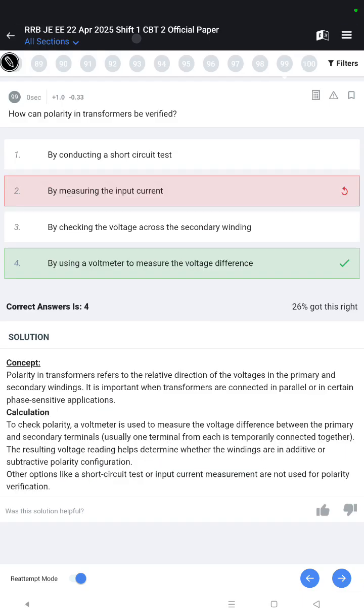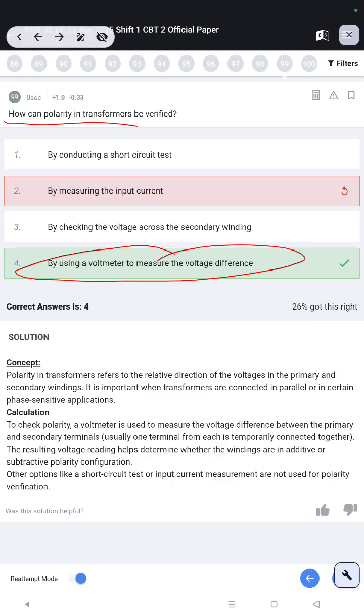How can polarity in a transformer be verified? By using a voltmeter to measure the voltage difference. To check polarity, a voltmeter is used to measure the voltage difference between the primary and secondary terminals. Usually, one terminal from each is temporarily connected together. The resulting voltage reading helps determine whether the windings are in additive or subtractive polarity configuration.